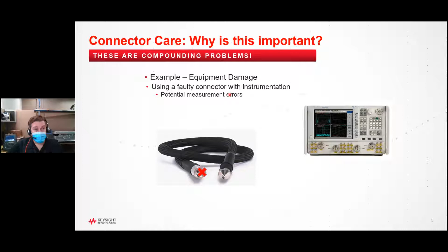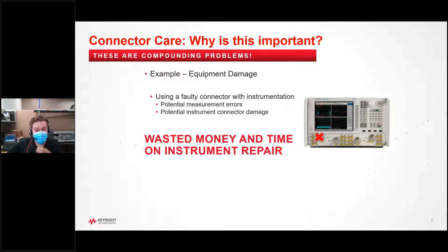So this will give you not only bad measurements, but it'll also damage the connector on the PNAX. So then next time you use that PNAX, that port, the errors will propagate to the measurement unit. And then you don't figure out what's going on, and you move on with life. Things look a little weird, so you connect another cable back to that port. And now you've just ruined 2 cables, and you still have the ruined port of your PNAX. So now you can see where this is going, and how those problems can cascade.